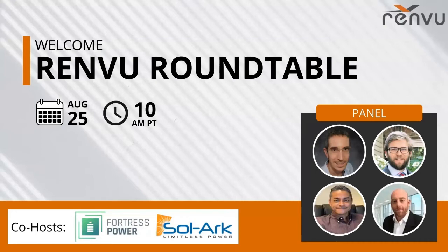There's a follow-up question from Sarah: if you want a backup system that works with your grid-tied 20 kilowatt solar system, you would stack multiple 12Ks together if you wanted to use all of that 20 kilowatts of PV. Another option, if you just want basic backup for a few critical items, is that maybe the primary driver of the 20 kW system is bill savings or some other motivator, but you don't necessarily need all 20 kilowatts for your critical backup.